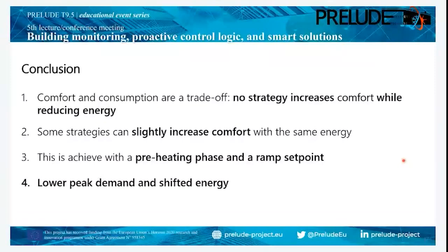So just a couple of conclusions, which we already mentioned: comfort and energy consumption are a trade-off, so there is no magical solution. But if you apply a more intelligent schedule for the heating system, you can get slight comfort increases along with a reduction in peak heating demand, which also reduces the required system design size. This is done by preheating the system with a ramp schedule rather than a stepwise one. That's it, thank you.